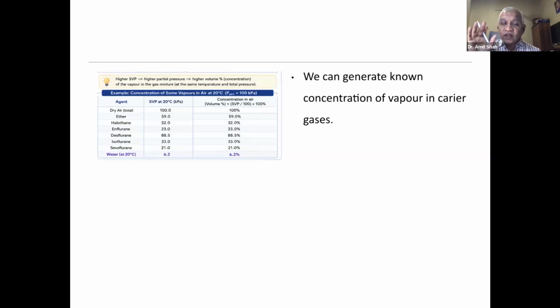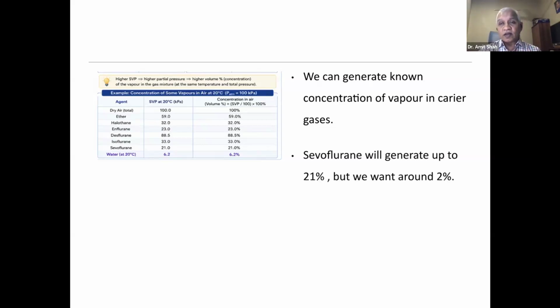So with this understanding, now we understand that we can generate a known concentration of a vapor in a carrier gas. So when you pass a carrier gas through any container, we can identify the known concentration of that particular agent. So if we are passing, say, oxygen through a container which has sevoflurane, it will have a 21% concentration. So it can carry up to 21% of sevoflurane in that particular carrier gas. So sevoflurane can generate up to 21%.